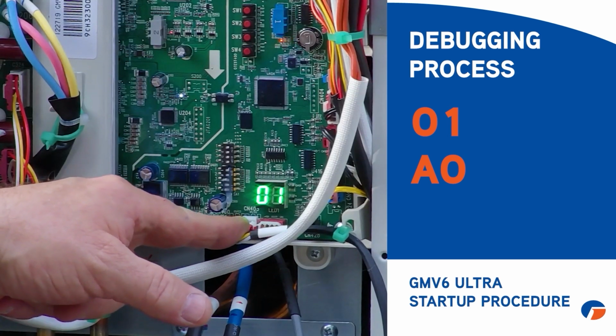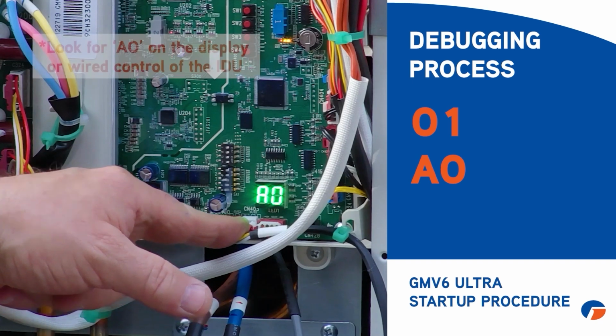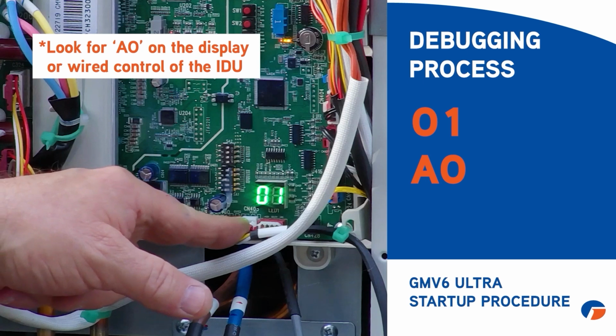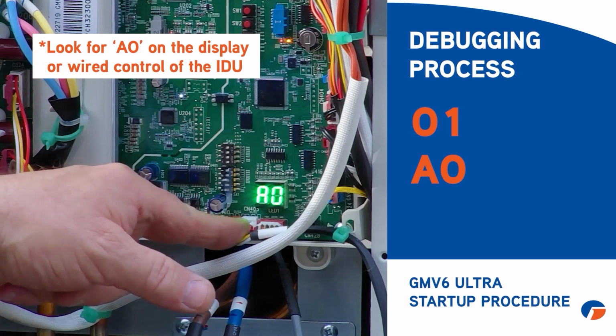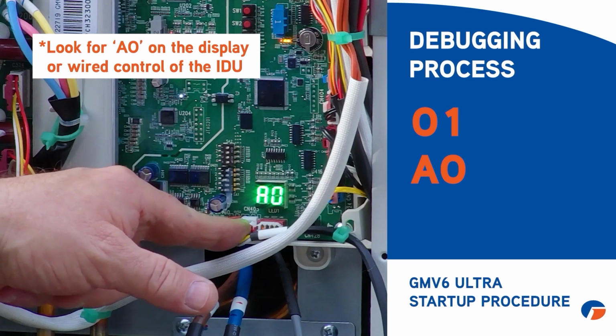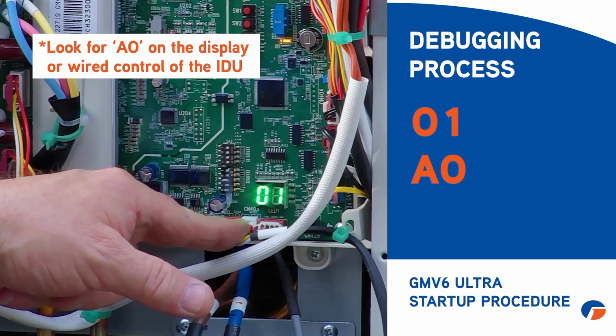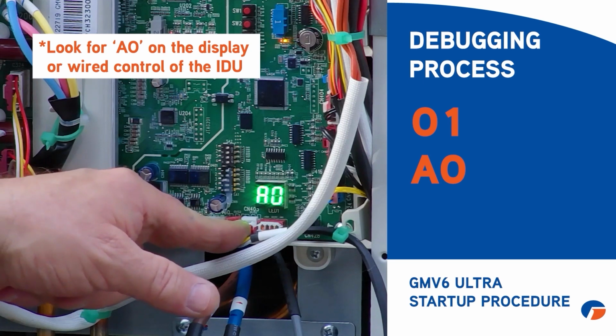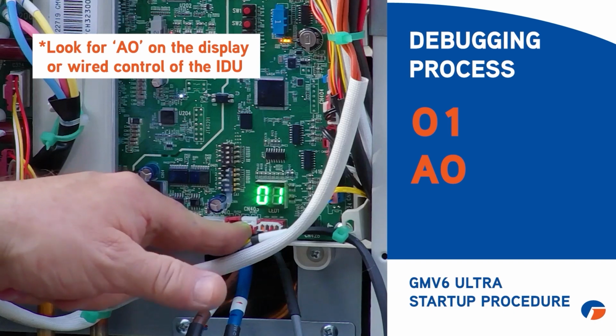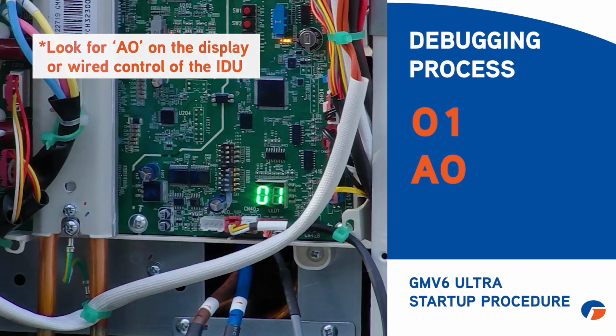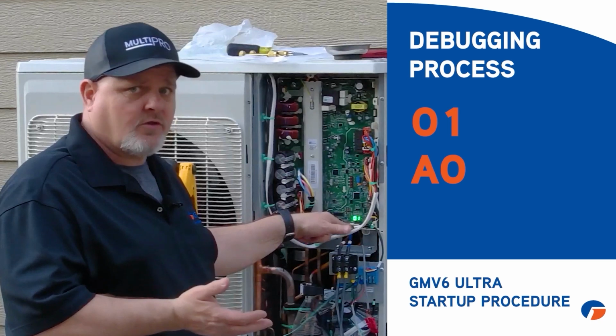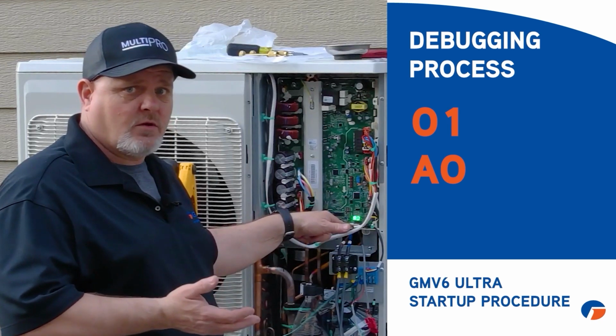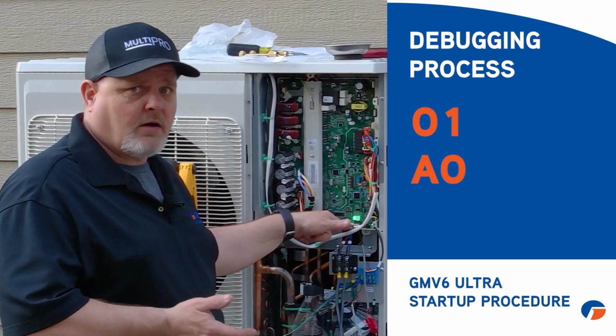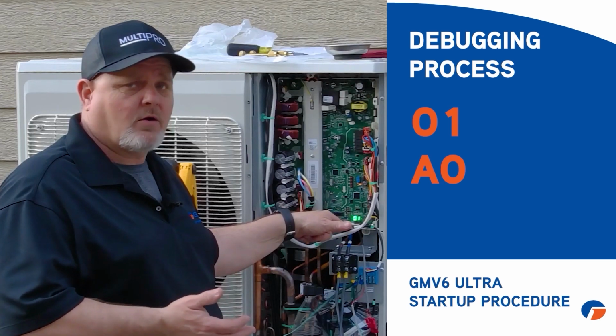Before you put it through debug, I would recommend you go inside. If it's got a display right on the wall mount, it'll say AO. If it's a ducted unit or a cassette, then it's going to say AO on the wired controller. Any of those machines that don't say AO, you don't want to start debug yet. Let's check power, make sure it's got 230 volts, because all the GMV indoor units are 230 volt powered. We don't have any 115 volt powered ones.